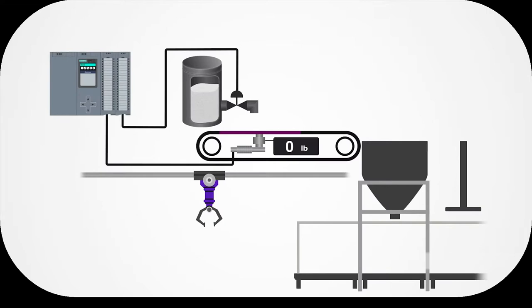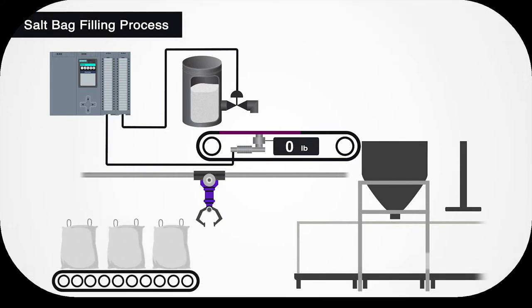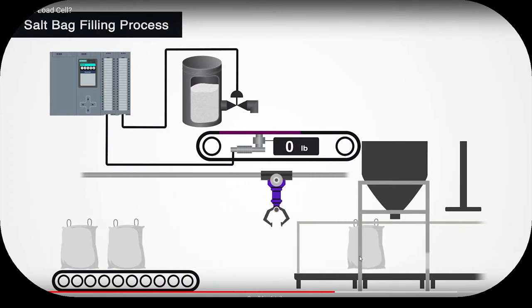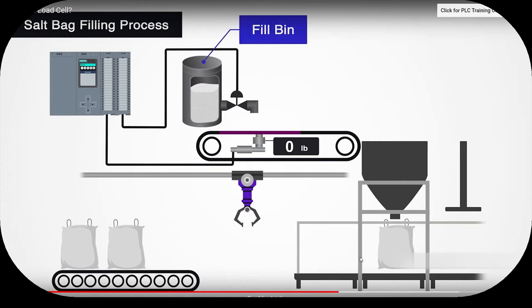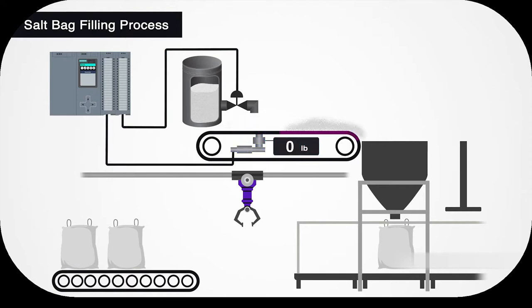The first application is a salt bag filling process. Empty bags are loaded into a machine where arms swing down, pick up a bag, and place it underneath a funnel. Above the funnel is a fill bin that dispenses salt onto a conveyor belt with a built-in load cell to dispense the correct amount. As the fill bin dispenses salt, the load cell gives an analog input to a PLC showing the current weight. Once the reading is close to the full bag weight, the fill bin closes to a trickle until the correct weight is reached, then the salt drops into the funnel and the bag is sealed.